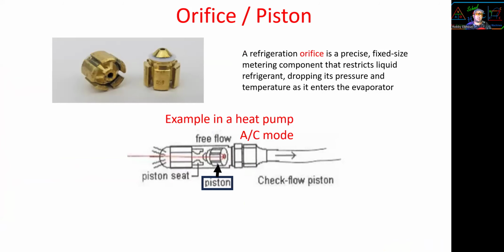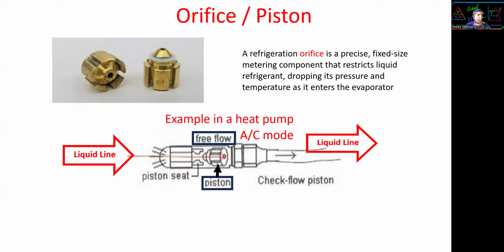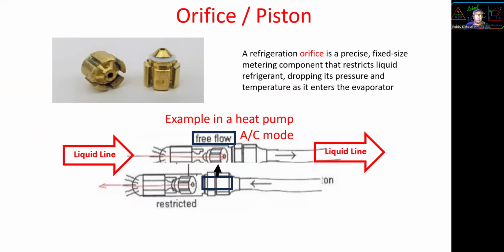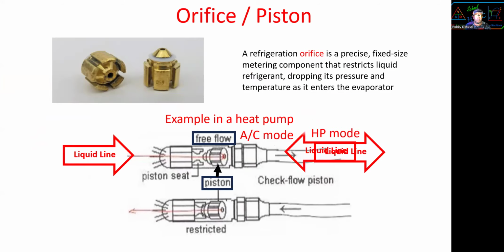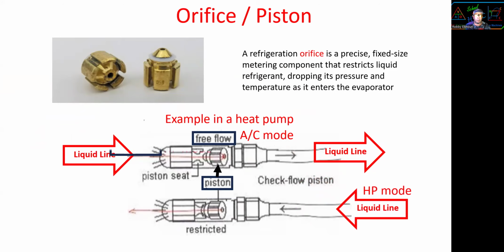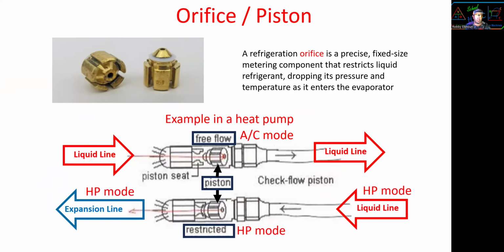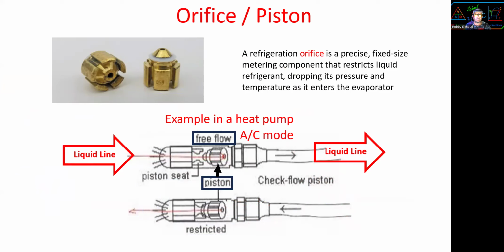All right, now the orifice piston. The orifice or piston is a fixed size metering device that restricts the flow of refrigerant, dropping the pressure and temperature as it enters the evaporator. Same as a cap tube. So the example is a heat pump system in AC mode. The piston has liquid in, free flow, liquid line in, nothing happens. Now, heat pump mode, liquid in, the piston is restricted, and expansion. All right, so in AC mode, the piston doesn't do anything.